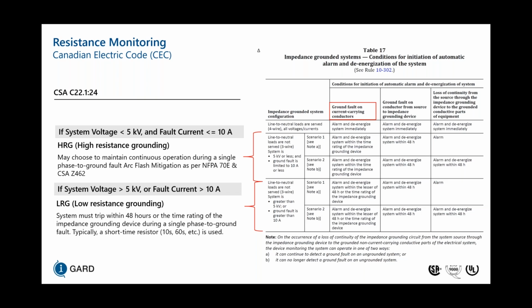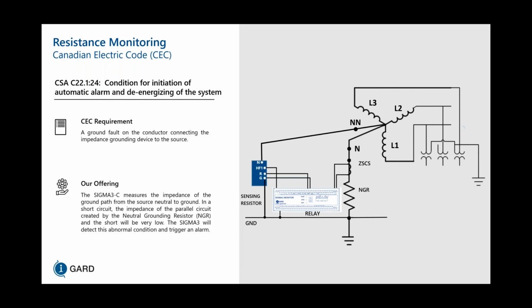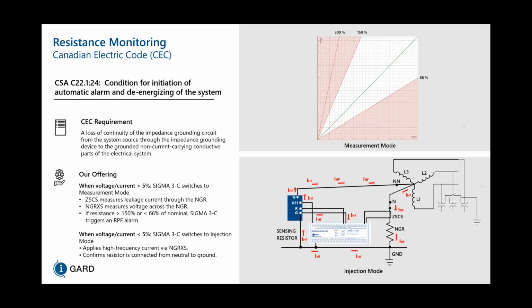So make sure to use a 10-second or 60-second rated resistor rather than a continuous rated resistor if you know that you're going to be tripping on first fault. Now, in terms of the detection method, when we are injecting this high frequency AC signal and we don't experience the voltage drop across the resistor and it gets bypassed through a short circuit, we get our full signal back with just a minor drop across the line. And as a result, we can dictate that we're in a short circuit condition.